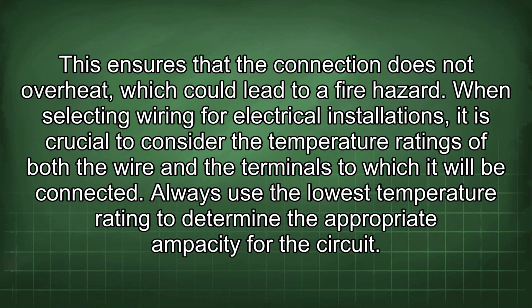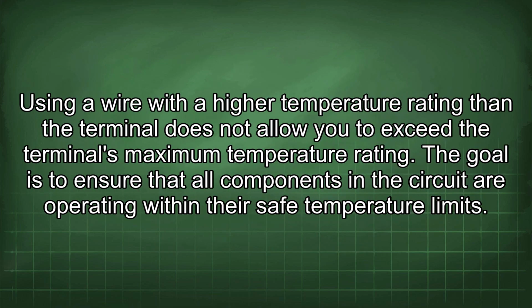This ensures that the connection does not overheat, which could lead to a fire hazard. When selecting wiring for electrical installations, it is crucial to consider the temperature ratings of both the wire and the terminals to which it will be connected. Always use the lowest temperature rating to determine the appropriate ampacity for the circuit. Using a wire with a higher temperature rating than the terminal does not allow you to exceed the terminal's maximum temperature rating. The goal is to ensure that all components in the circuit are operating within their safe temperature limits.